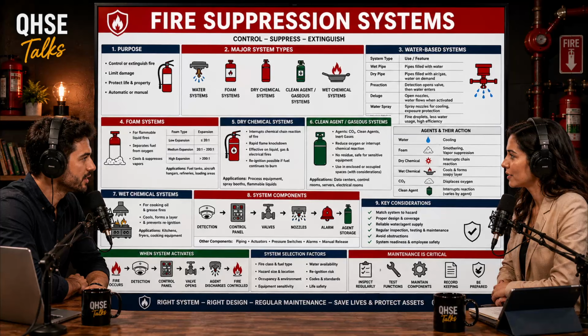Let's look at the specific OSHA rules for the construction industry. What exactly does OSHA mandate? OSHA requires employers to provide a fire extinguisher rated not less than 2A for every 3,000 square feet of protected building area, and critically, the maximum travel distance from any point to the nearest fire extinguisher must not exceed 100 feet. Let me stop you and push back on this regulatory logic.